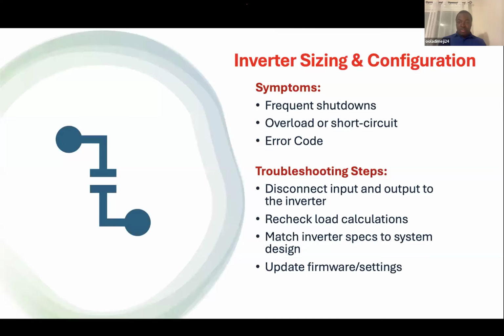For inverter sizing and configuration, what are the symptoms you see? Frequent shutdowns. You see some inverters go on overload, short circuits, error codes. Troubleshooting steps: look at the inputs, look at your outputs. Are you getting what you need from your inputs? Are you getting what is expected, based on your sizing, at the output?